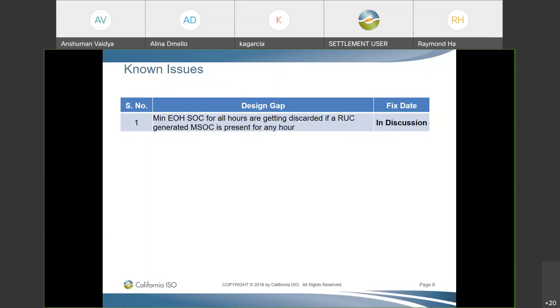Juan from CAISO: This relates to the design of the RUC-generated minimum SOC. Whenever under-generation conditions are triggered during the RUC, it generates minimum SOC for all hours of the trade date — including potentially zero values for non-critical hours. When this goes into the real-time market, those values are considered binding, which is why the software was designed to ignore the minimum end-of-hour state of charge bits. That is the potential design gap identified during testing, and we are following up internally to determine the best resolution.